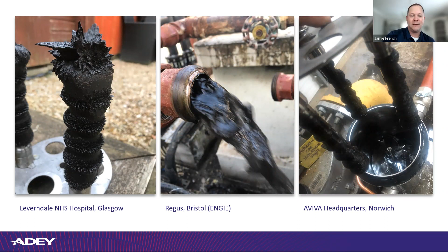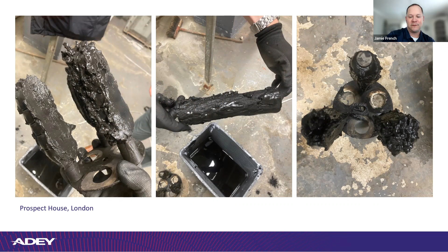This particular slide cracks me up because they have the magnets and the cartridge filters in there, so they're just wasting cartridge filters. They're just sucking up more of that magnetite with it. We always recommend going in with the magnets first until you get the water clean, and then start getting the non-magnetic debris with those cartridges. So here's the facts about it.